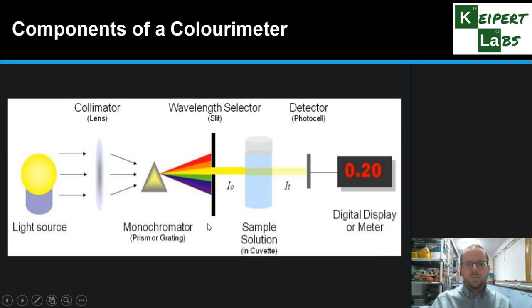So a monochromator. So the role of the monochromator is to split up these different colored wavelengths so that we can identify or isolate the wavelength that we're trying to actually pass through the sample. We have a wavelength selector or a slit or a diffraction grating that will actually eliminate the wavelengths we don't want to pass into the sample and then just allow the selected one to pass into it.